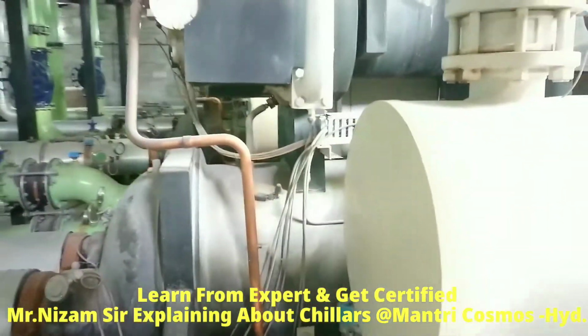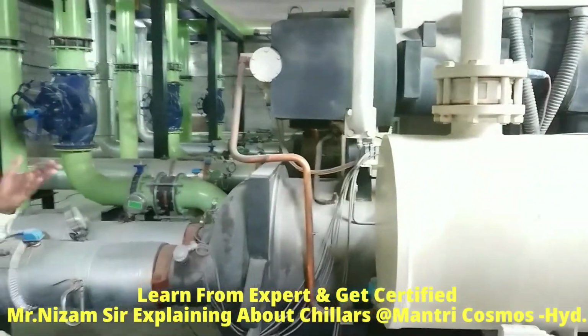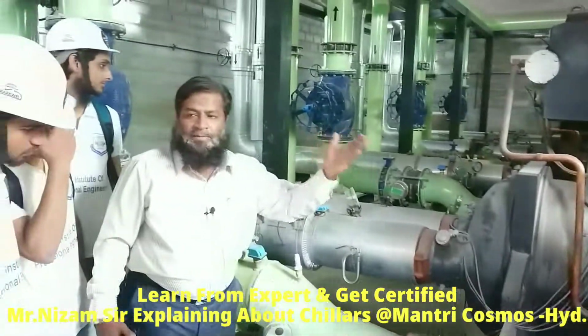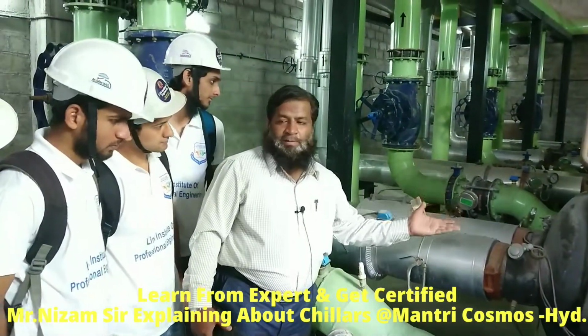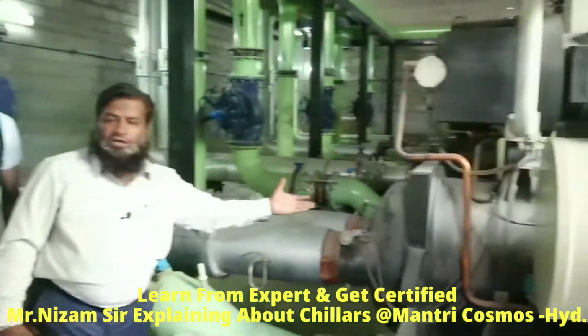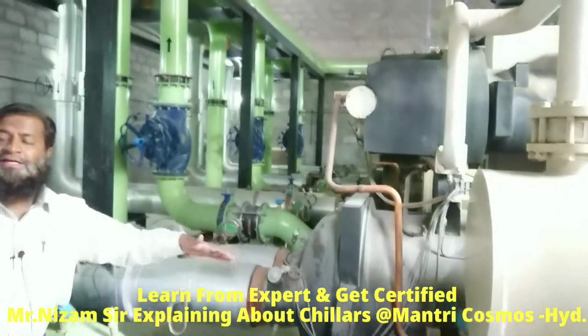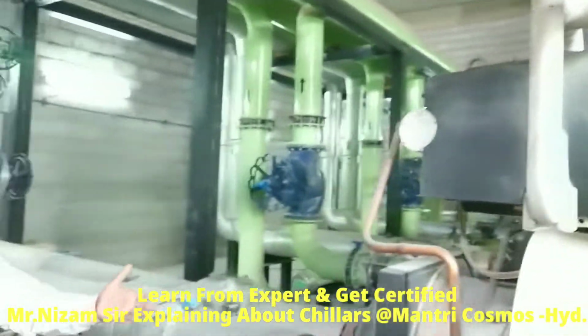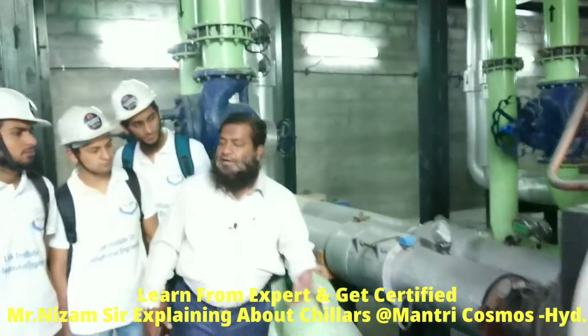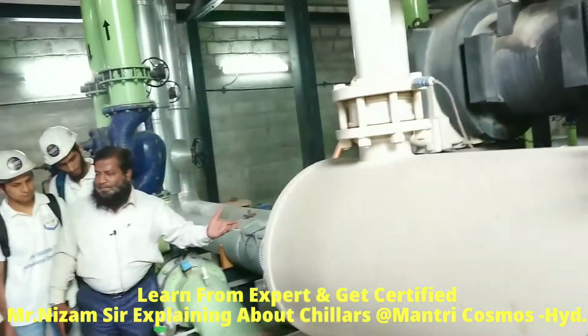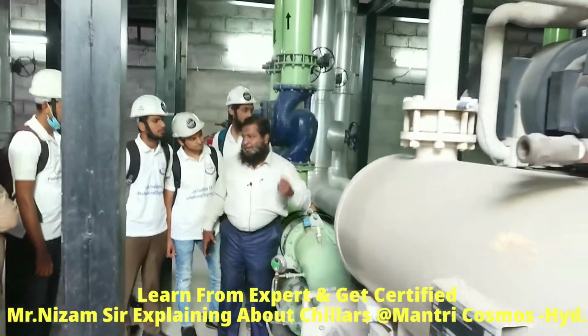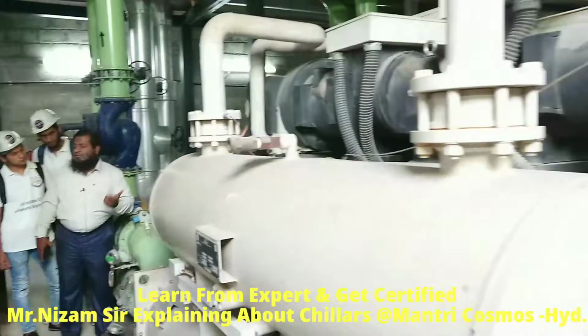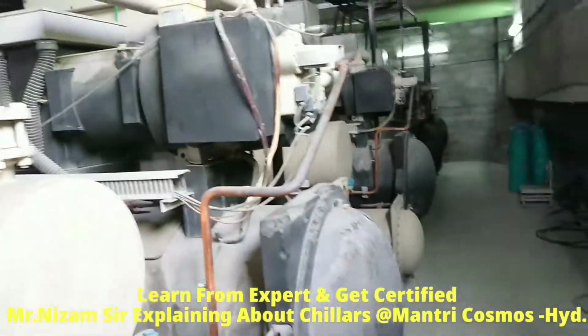Here we are using a chiller. This is the complete evaporation, where the low pressure, medium temperature liquid refrigerant from the expansion device goes to the evaporator, where evaporation happens. This is also a shell and tube type, but it is an evaporator, and the phenomenon is reversed a little bit, where the liquid, medium pressure, medium temperature refrigerant gets evaporated here, as the evaporator absorbs the surrounding heat, and the phase of the refrigerant changes from liquid to vapor, and simultaneously it leaves the cooling effect.